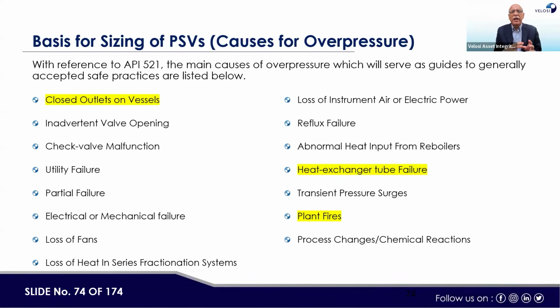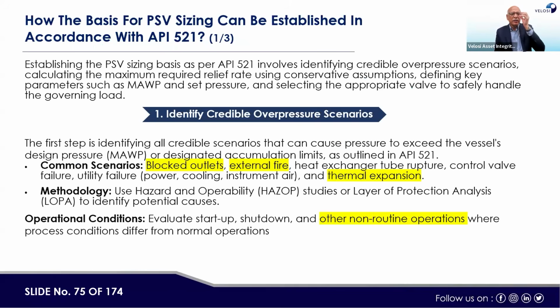In this way, the sizing basis of the PSVs is selected: what the scenario could be, how this high pressure would be generated, and for relief of that high pressure, what flow rate we need to exit through the PSV. This is the API 521 basic requirement. Common scenarios I already explained are a blocked outlet, external fire, heat exchanger tube failure, control valve failure, and utility failure. There could be any scenarios, and I only explained two.